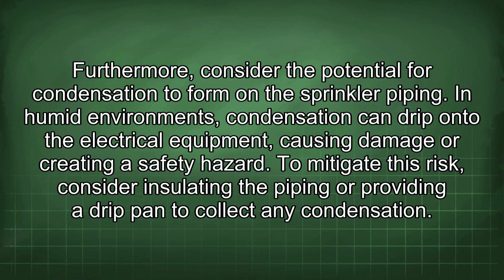Furthermore, consider the potential for condensation to form on the sprinkler piping. In humid environments, condensation can drip onto the electrical equipment, causing damage or creating a safety hazard. To mitigate this risk, consider insulating the piping or providing a drip pan to collect any condensation.